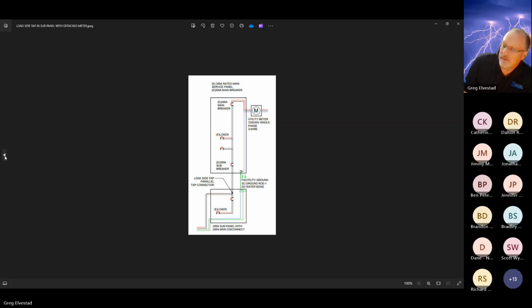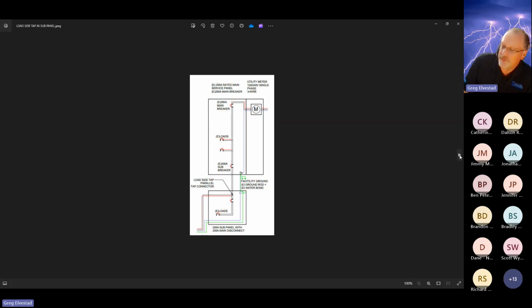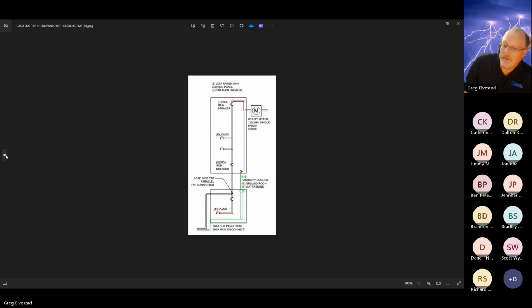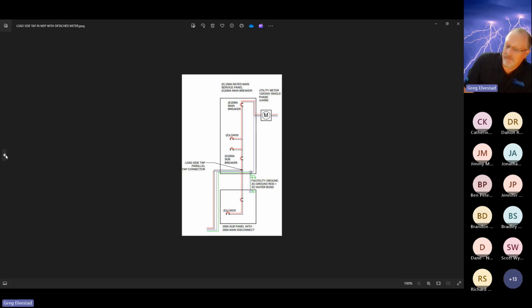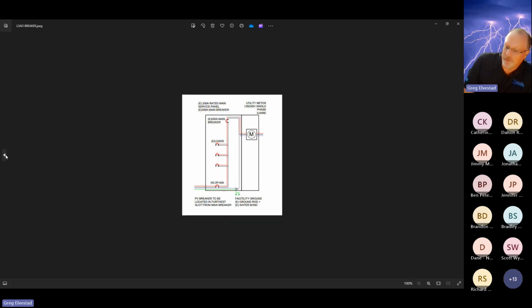Another option, what are we showing here? Let me check the difference between these two. Not much difference. Again, tapping outside versus inside, multiple different combinations. Here is probably the most common one you've ever seen: load side breaker interconnection. Very, very simple. Probably 90% of the designs you ever do are going to be this. So you take the bus rating, 200 amps, multiply by 1.2, which gives you 240. Then you subtract the main breaker rating, 200, which gives you the ability to land 40 amps of solar safely and conveniently.